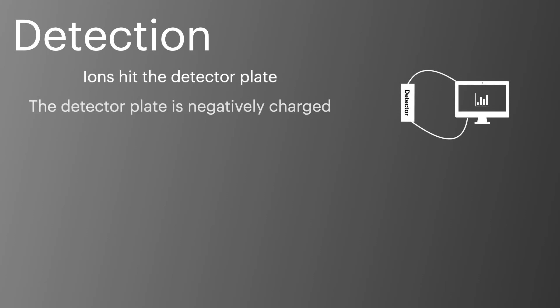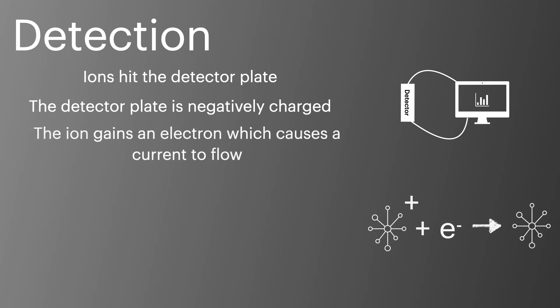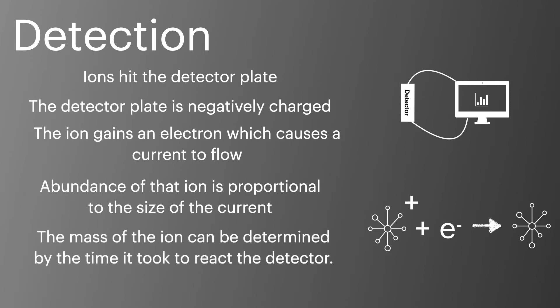Detection is the final step of the mass spectrometer. Ions hit the detector plate after travelling down the flight tube. The plate is negatively charged, and when positive ions hit the plate, they cause a current to flow. The abundance of that ion is proportional to the size of the current that flows, and the mass of the ion can be calculated using the time it took to arrive at the detector.